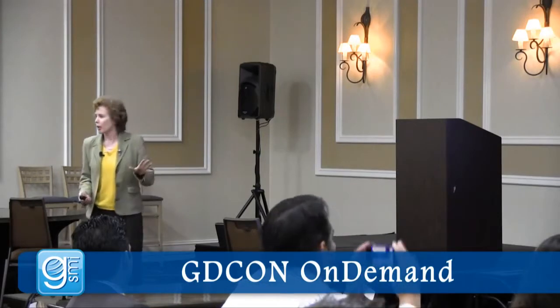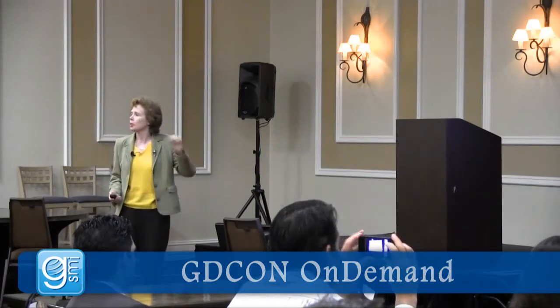Instead of each one having tier 4 level reliability with backup systems and its own diesel generator, let's feed the utility power and diesel generators through a power ring, which provides greater redundancy where we need it, like tier 4 in the middle, and very little redundancy where we don't need it. So in the event of a grid failure, you've got utility power coming in, 1030 kW at the top.